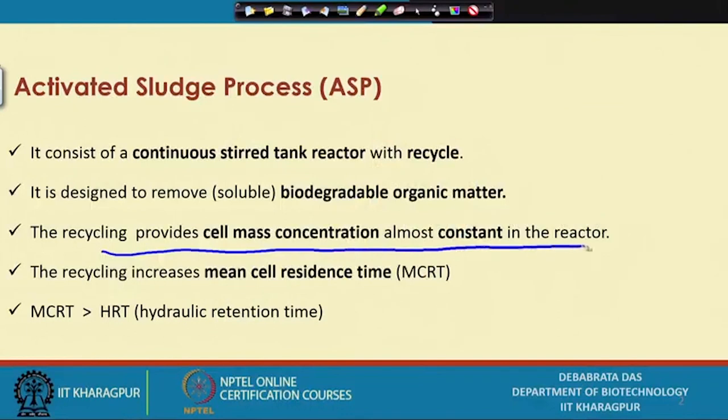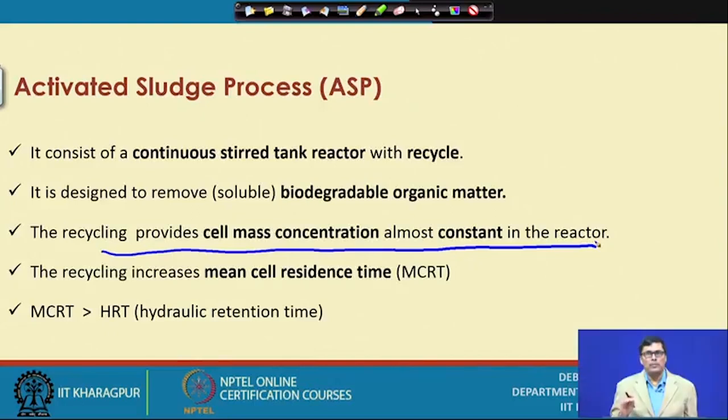In the biological process, if there is any soluble organics present in the wastewater, bacteria can easily utilize this organic matter for growth and multiplication. The soluble organics are converted into insoluble biomass. This insoluble biomass can be easily separated out — if you separate it out, you will find a clear liquid. That is why the activated sludge process is largely used for wastewater treatment. The recycling provides an almost constant cell mass concentration in the reactor, and the main purpose of recycling is to maintain uniform cell mass concentration so the rate of reaction in the reactor remains constant.